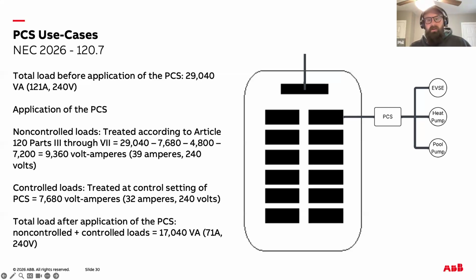In this grouped load monitoring example, 3 different loads are placed under the control of a power control system: an EVSE rated at 7,680 VA, a pool pump rated at 4,800 VA, and an HVAC heat pump rated at 7,200 VA. All 3 loads are supplied from a single 40 ampere branch circuit protected by a 40 amp overcurrent device. The PCS is programmed to monitor the current on that 40 ampere branch circuit and dynamically adjust the operation of the EVSE, pool pump, and heat pump so that their combined demand never exceeds the PCS control limit.